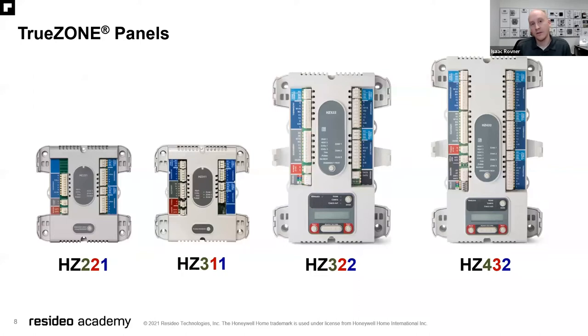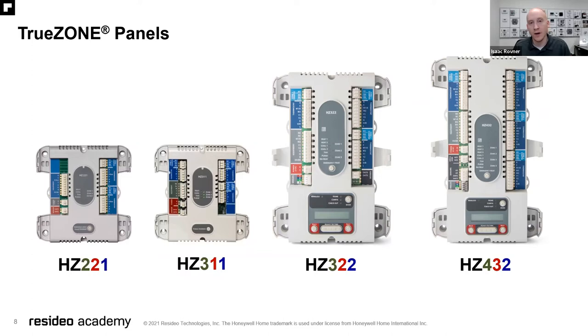The second digit is the number of heat stages and the third is the number of cooling stages. So for the HZ322, that's three zones, two heat, two cool. Within the literature and on our website, it's going to clearly label and provide the specs, so you'll know exactly what panel you need for the job.